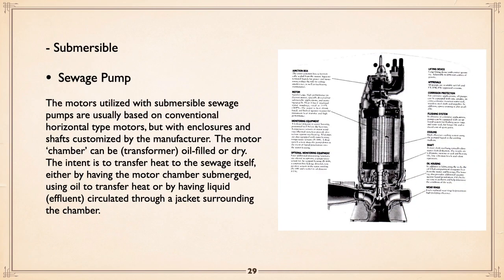Submersible motors basically are designed based on conventional horizontal motors, but with customized shafts and enclosures by the manufacturer. The motor case can be dry or filled with oil. If it's filled with oil, the heat will transfer to the casing itself, which radiates out into the sewage wastewater and cools the thing. If you go dry, then basically they will flow liquid through a double wall casing and allow it to cool the casing. And of course the motor is up tight against that, so it will transfer the heat.